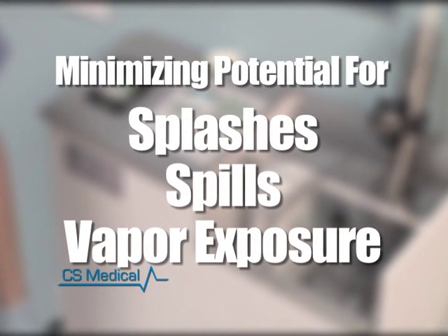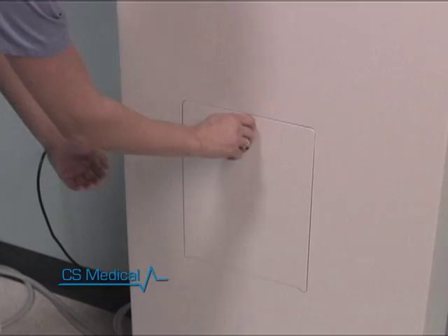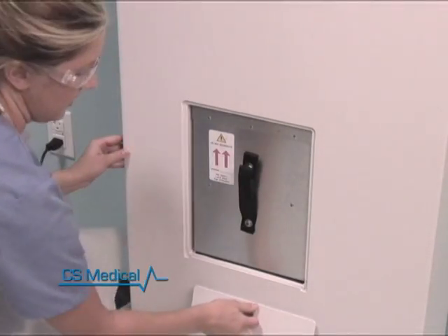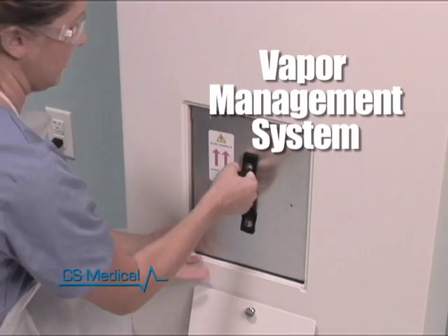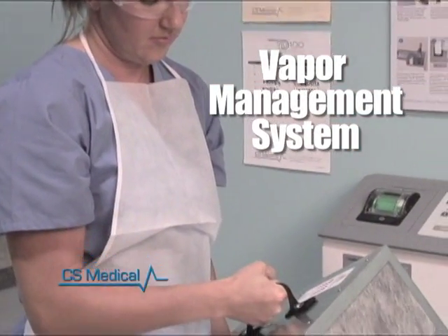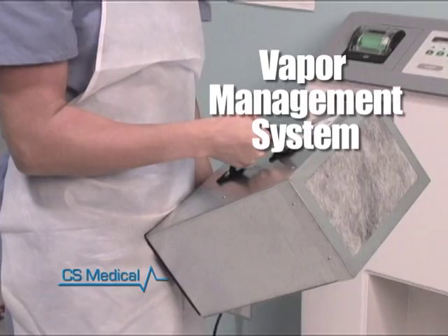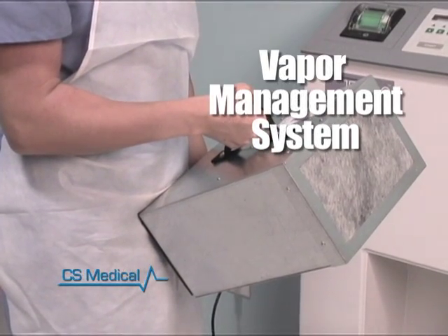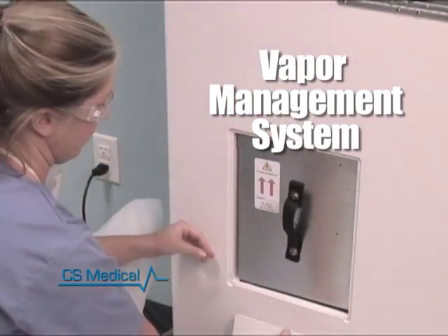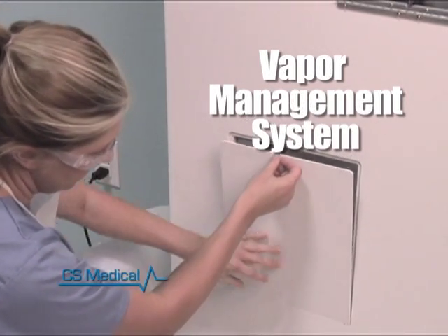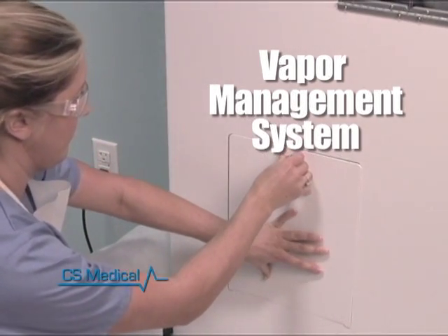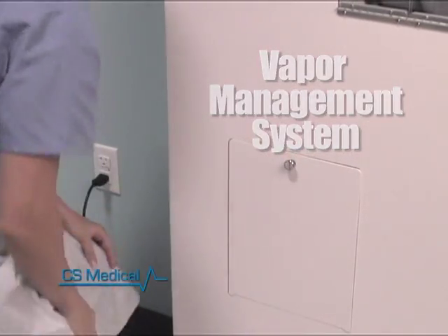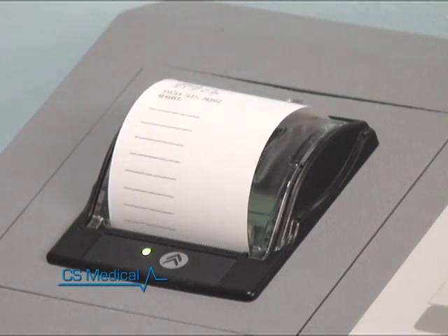The manual process of using bowls and tubes cannot provide you with the same level of protection as the TD100. The TD100 incorporates an advanced vapor management system that minimizes the potential for exposure to disinfectant vapors. The vapor management system utilizes a special bonded carbon filter designed to absorb and neutralize glutaraldehyde vapors. The filter is easily changed by opening the vapor management system door, pulling the saturated filter out, and putting a new one in. Looks like the TD100 cycle is complete.